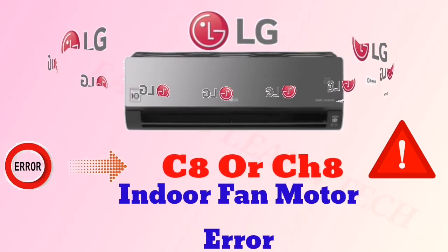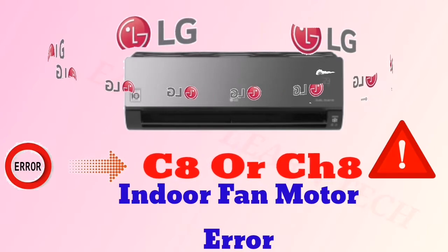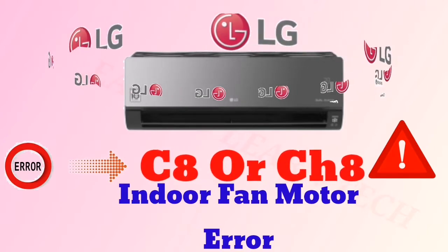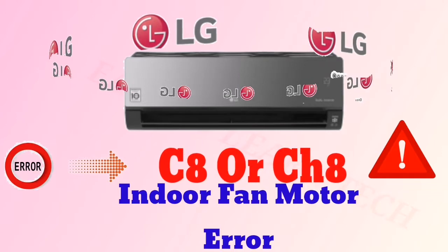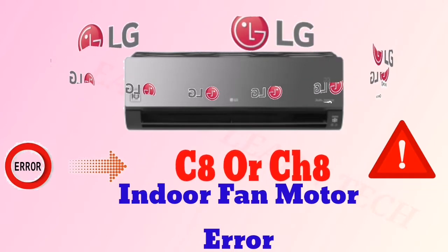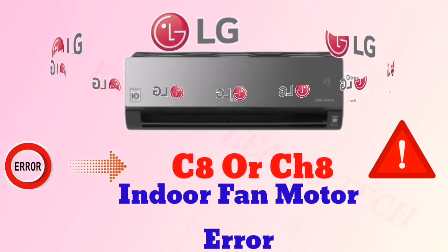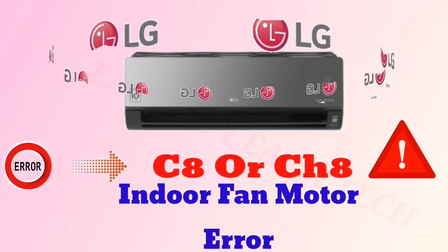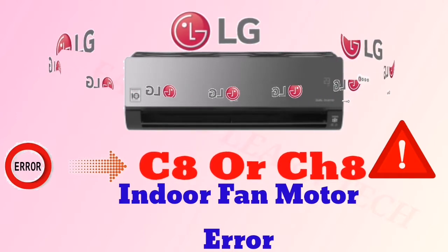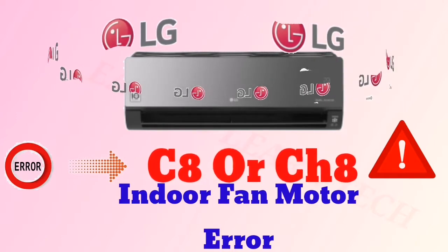And if you are getting the output supply properly, it means your fan motor is faulty. You can also check the resistance of your fan motor, and if the fan motor resistance is okay, that means the indoor PCB is faulty. Then you have to change the indoor PCB or the fan motor, and then your unit will be in working condition.